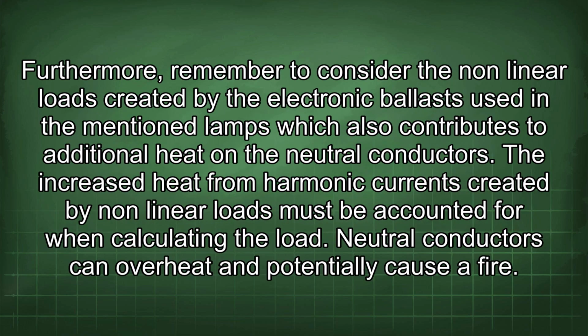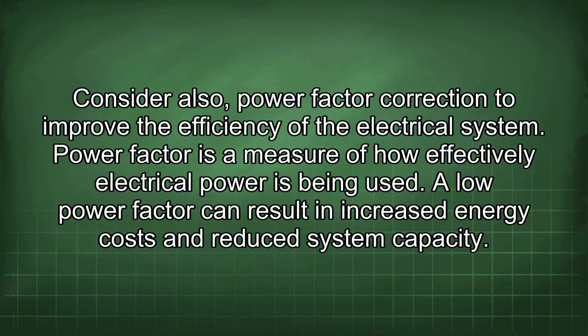Furthermore, remember to consider the nonlinear loads created by the electronic ballast used in the mentioned lamps, which also contributes to additional heat on the neutral conductors. The increased heat from harmonic currents created by nonlinear loads must be accounted for when calculating the load. Neutral conductors can overheat and potentially cause a fire. Consider also power factor correction to improve the efficiency of the electrical system.